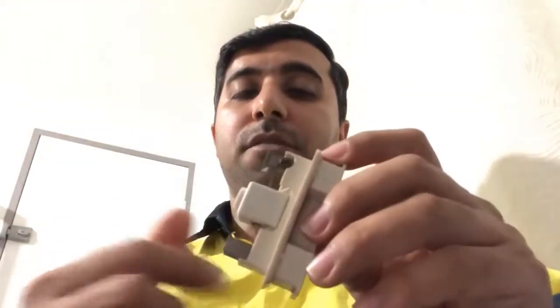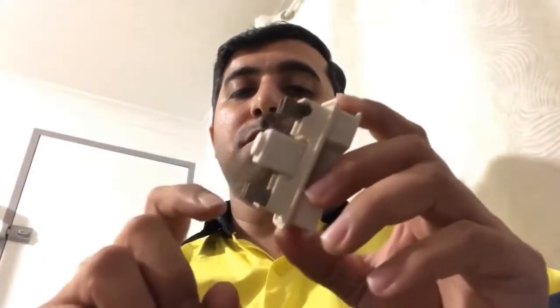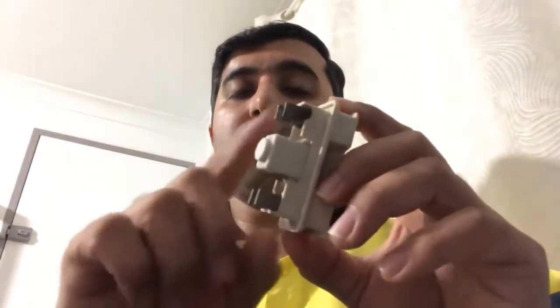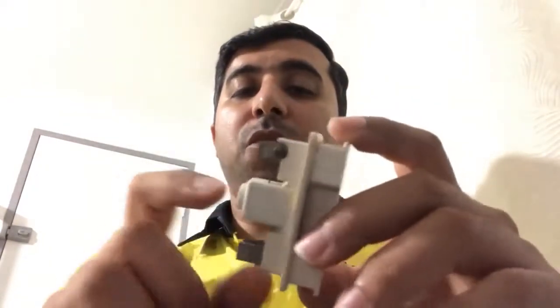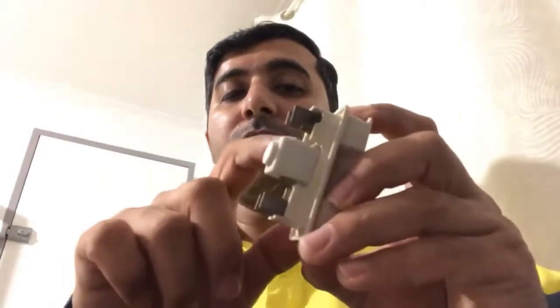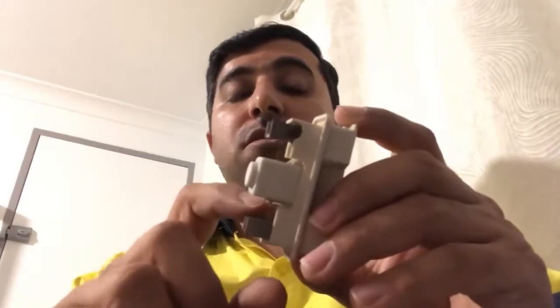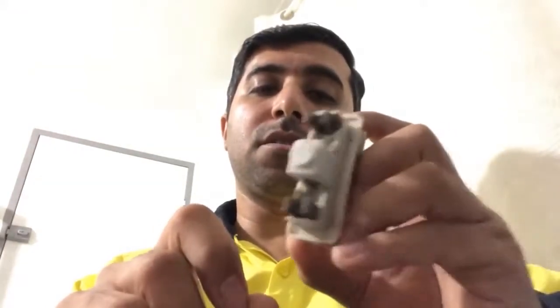The disadvantage of using the fuse, apart from being very basic, was that everything works based on the wire that connects these two together. If you mess up with the wiring, like this one where they used the double strand, or if you use the wrong size of wire, you mess up the protection that this is supposed to provide for the cabling inside the house.